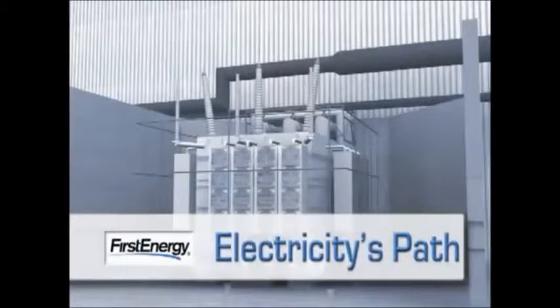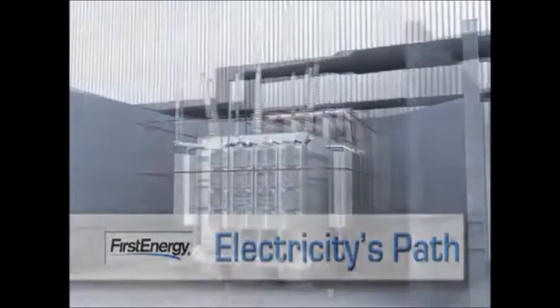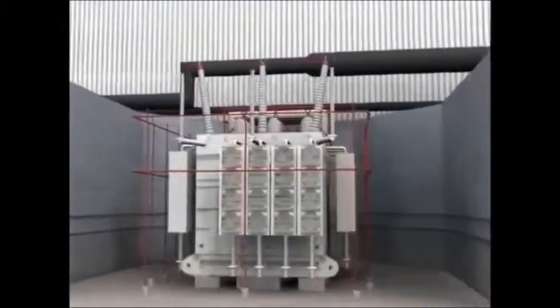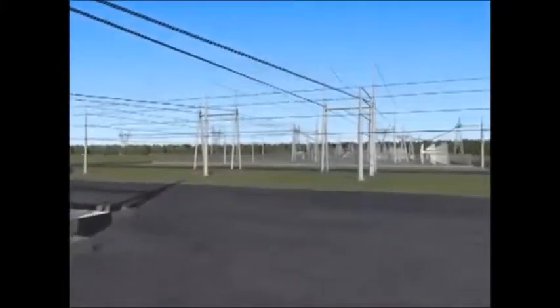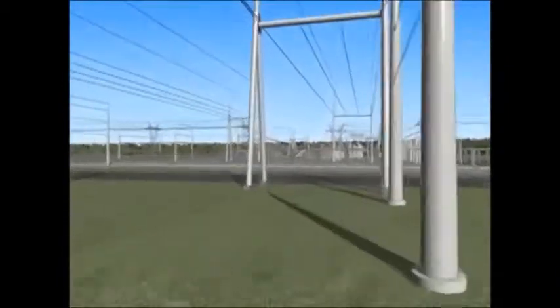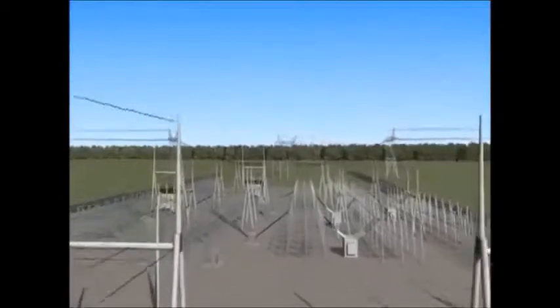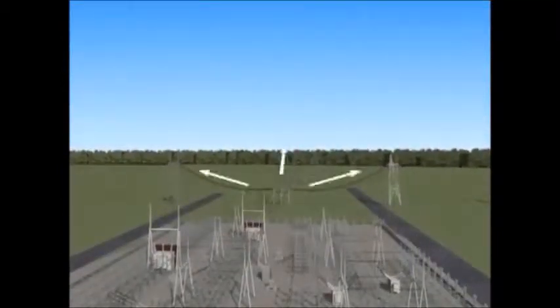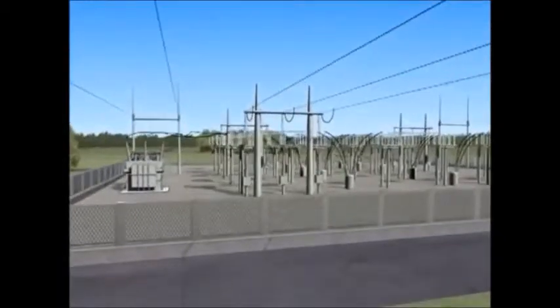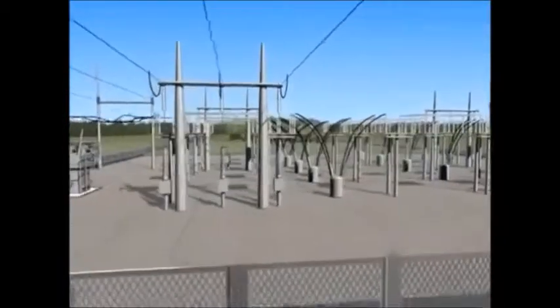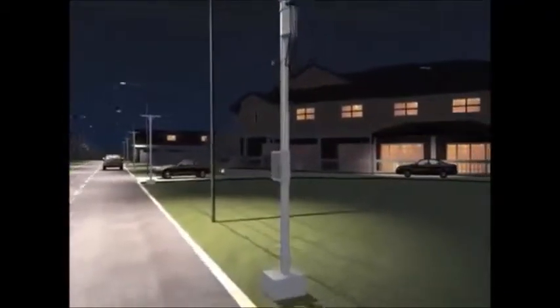Now that we've taken a look at how electricity is produced and some of the environmental control protection systems used at our plants, let's take a look at how the electricity is delivered to our homes and businesses. Transformers located just outside the plant boost the power from 18,000 volts to 345,000 volts, so it can travel long distances over transmission lines to where it is needed. Substations located along the path reduce the voltage so it can be moved along distribution lines attached to the utility poles. As the electricity nears customer locations, transformers on poles step down the power for use in homes and businesses.